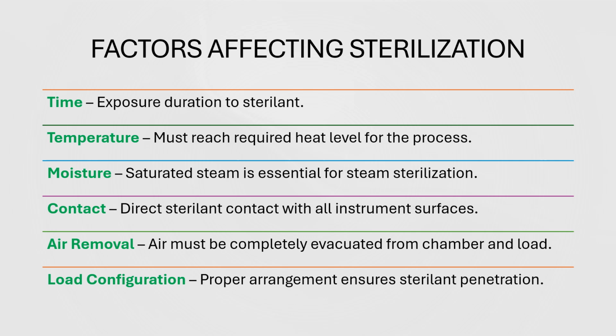Air removal. Complete removal is necessary for effective penetration, especially in pre-vacuum sterilizers. And how do we load the autoclaves? The load configuration: instruments must be arranged to allow free circulation of the sterilant, avoiding overloading and improper packaging. We also have to monitor all these variables to ensure proper sterilization and patient safety.